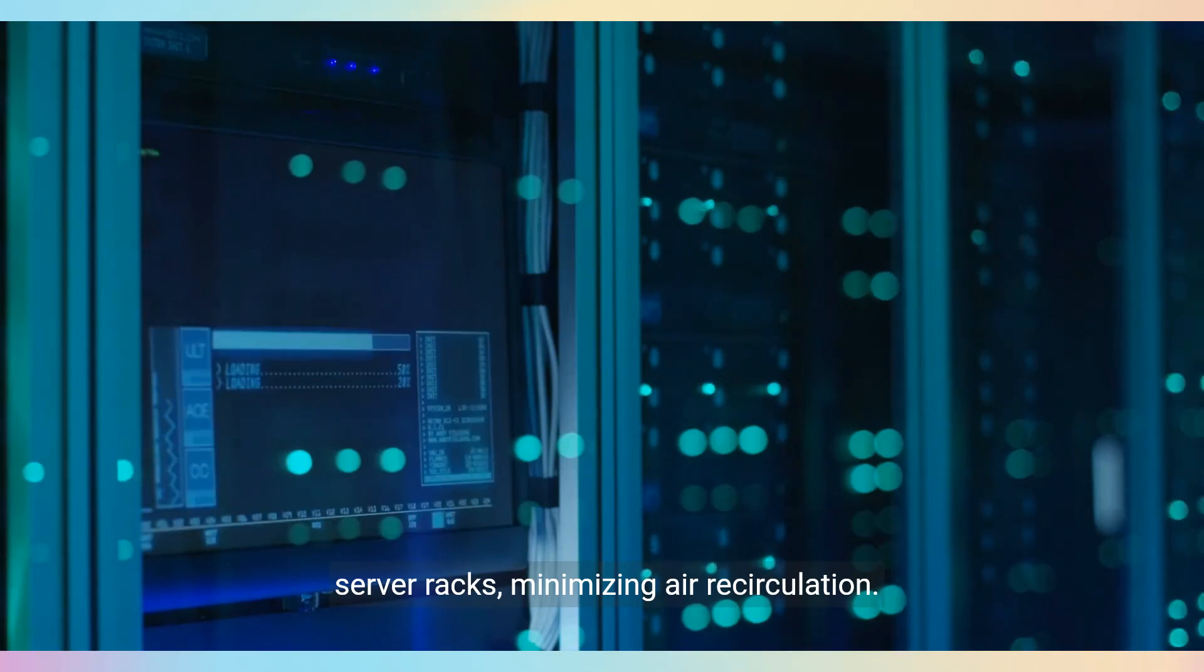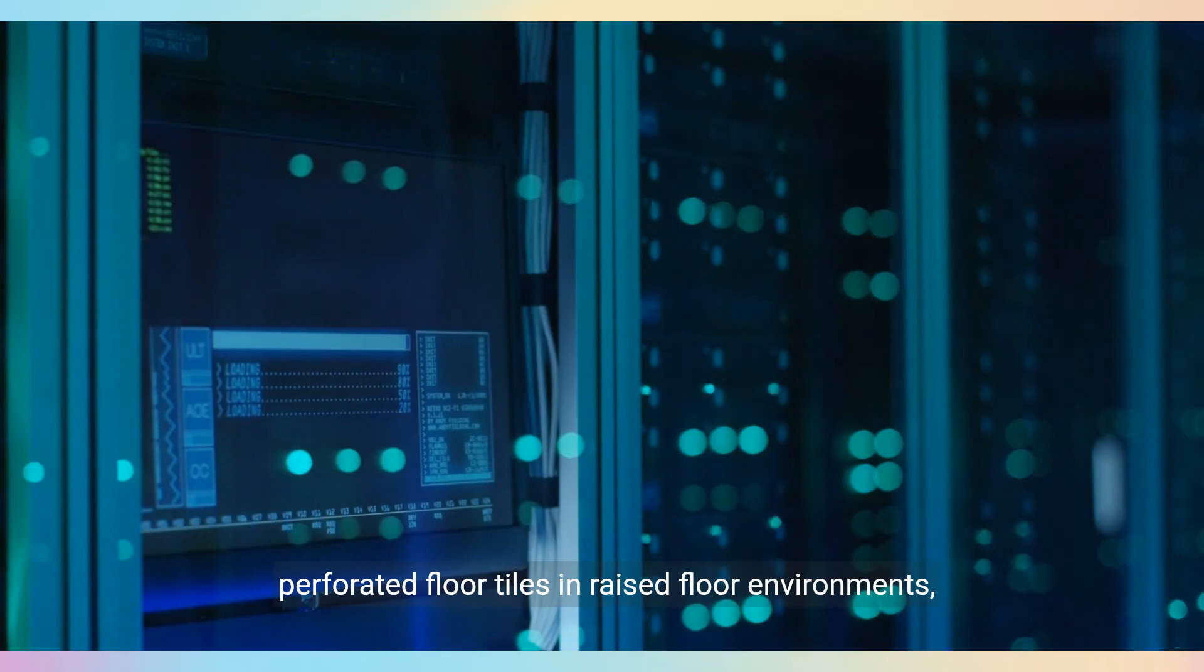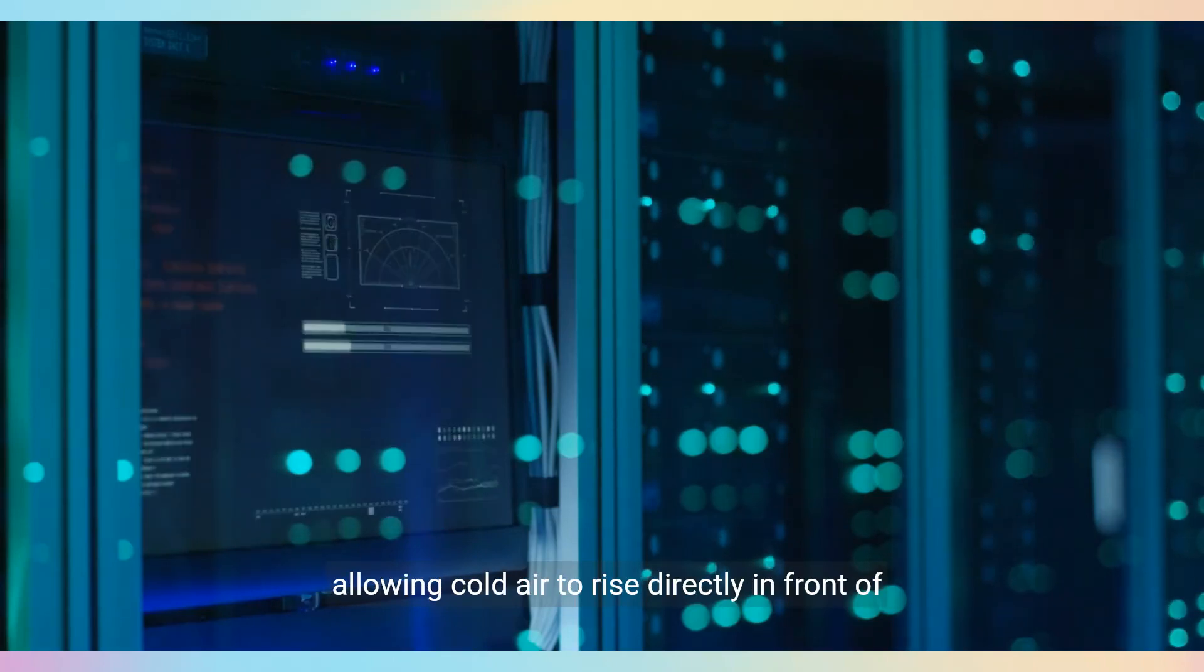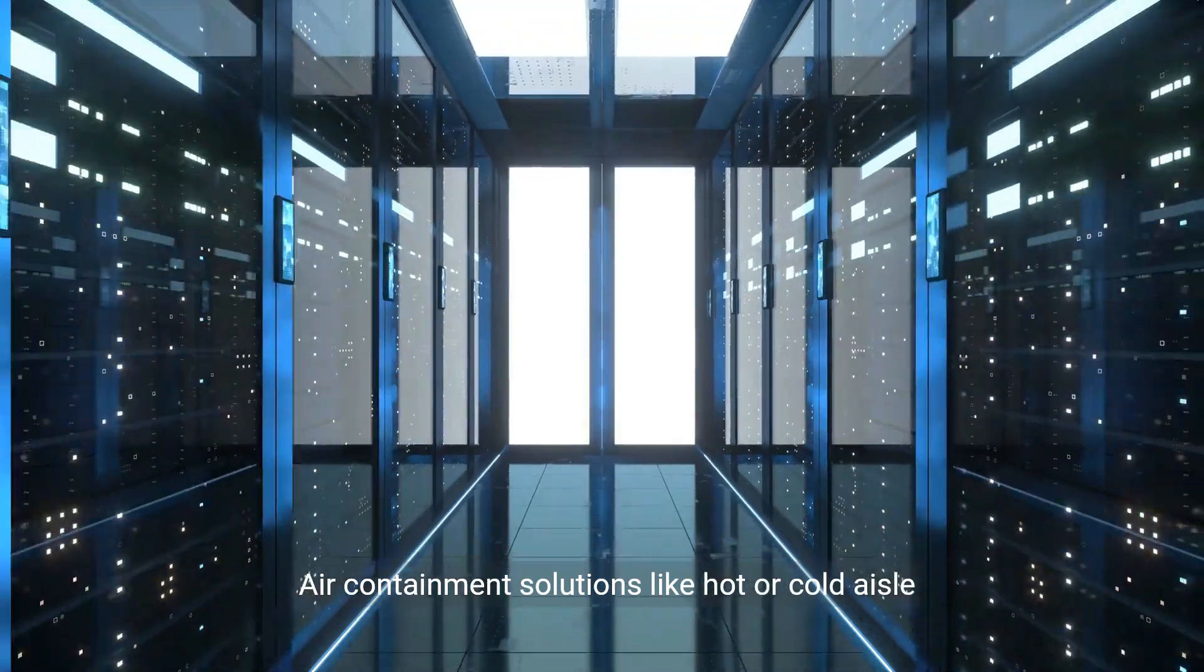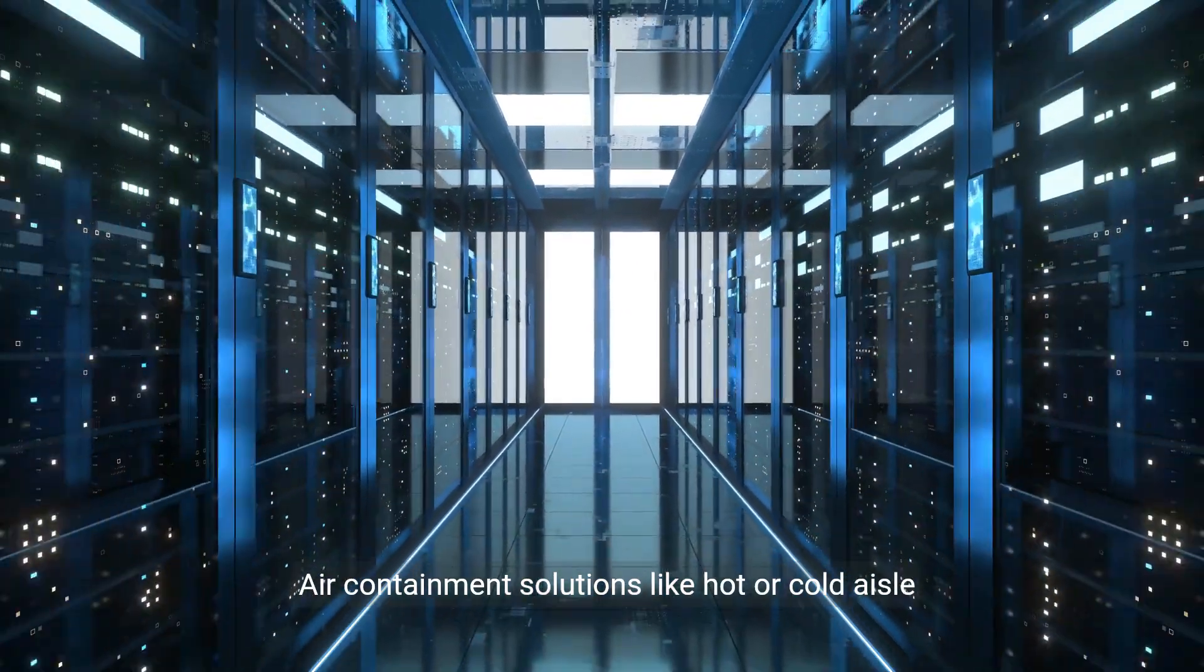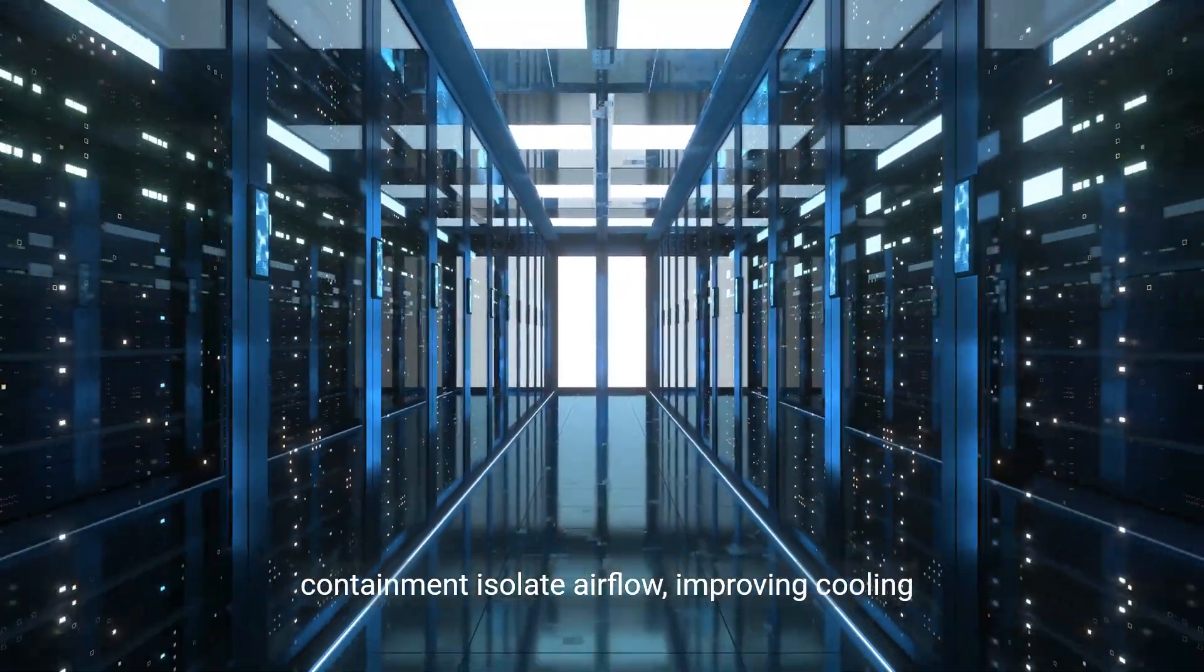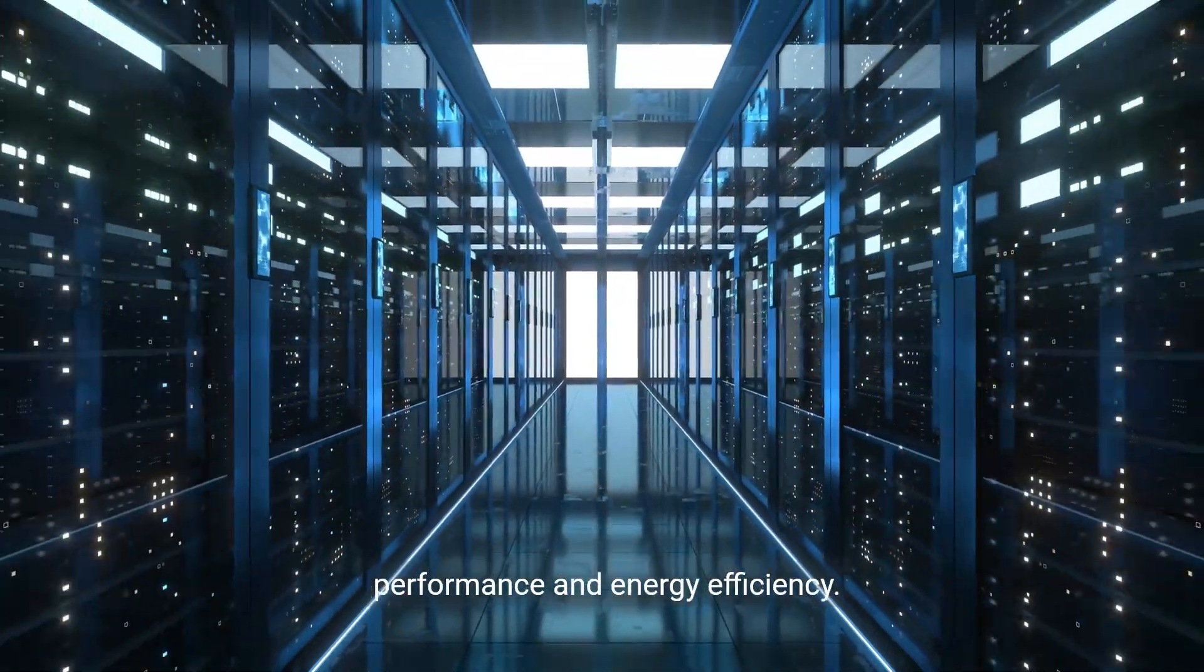Deploying blanking panels fills empty slots in server racks, minimizing air recirculation. Advanced airflow management includes placing perforated floor tiles in raised floor environments, allowing cold air to rise directly in front of server racks. Air containment solutions like hot or cold aisle containment isolate airflow, improving cooling performance and energy efficiency.